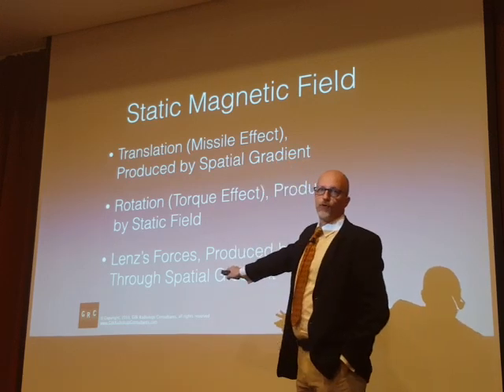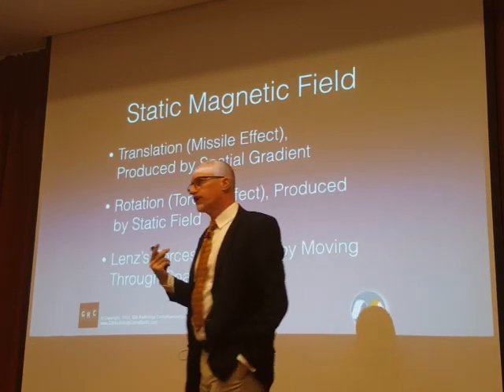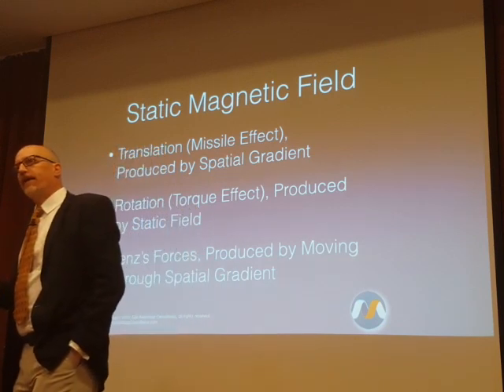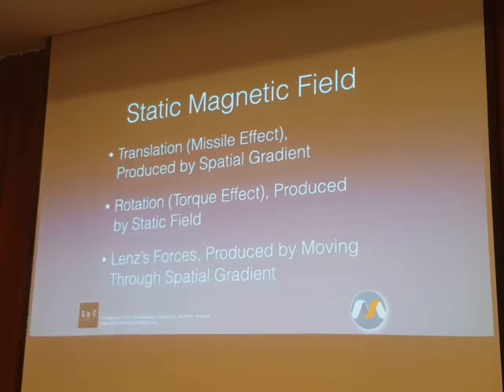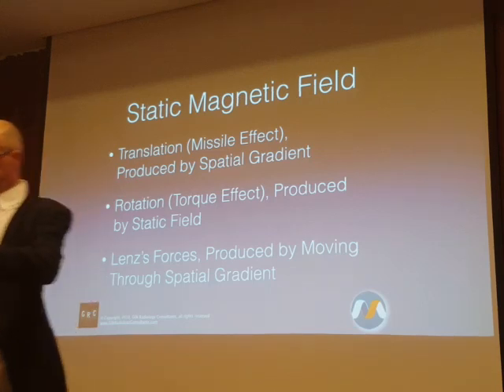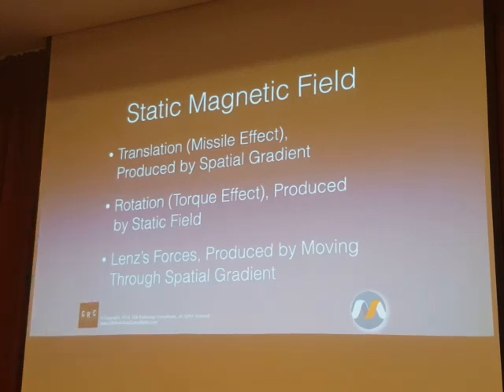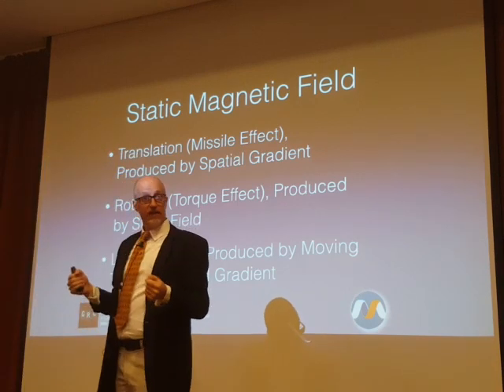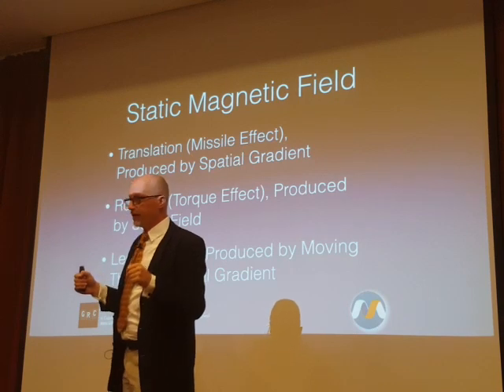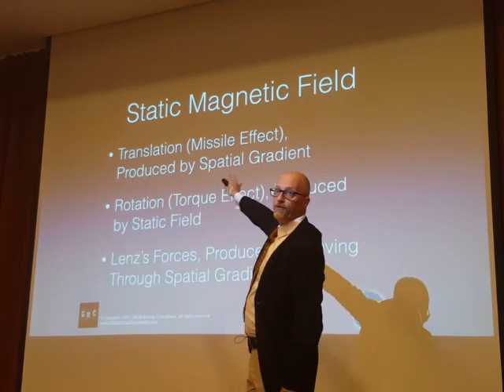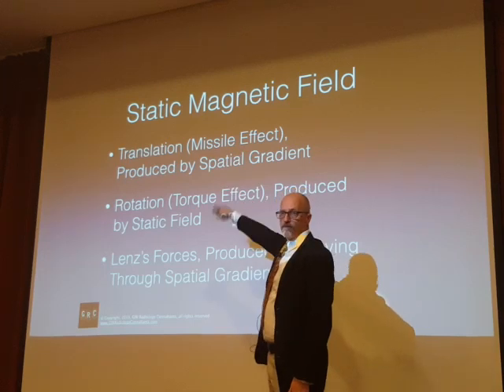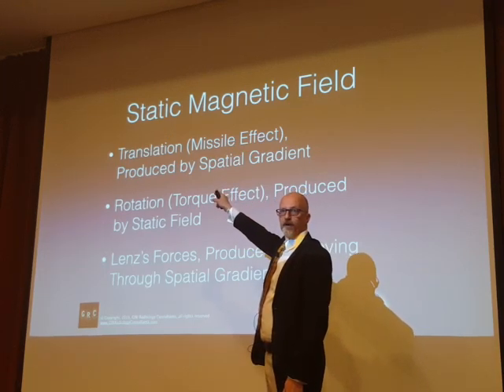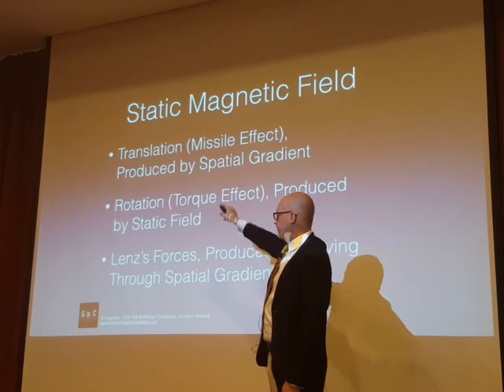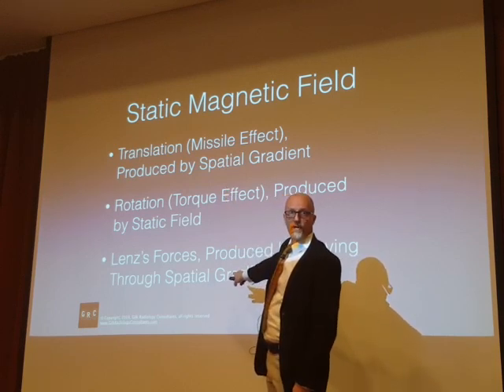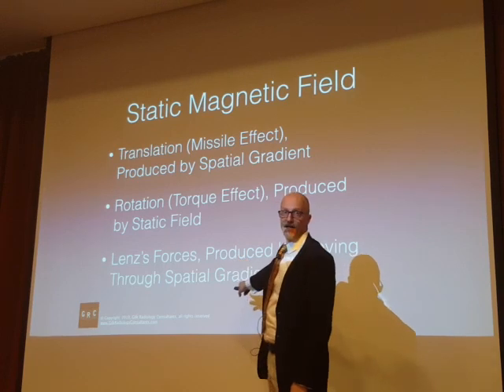There are also Lenz forces. Lenz forces are forces that are only produced through motion. So if this is the opening, the bore of the MR scanner, and I come with an electrically conductive item, it doesn't have to be ferromagnetic. Static magnetic field forces, torque and translation, only work on ferromagnetic objects. Lenz forces work on anything that is electrically conductive.